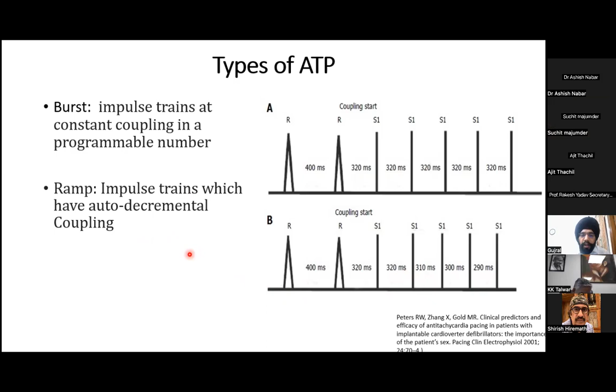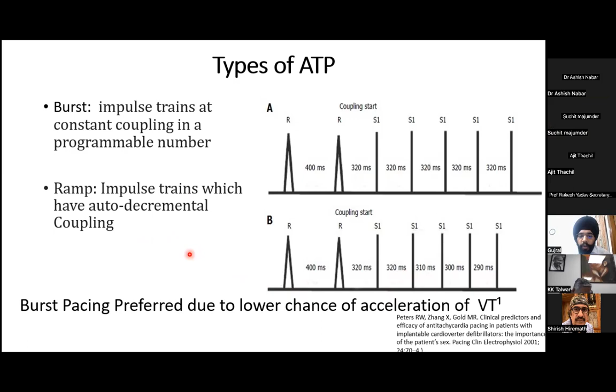Another type of ATP is possible, called ramp therapy. In that, the coupling interval between the pacing impulses is going to have a decrement, that is, it is going to reduce. The usual decrement that is set is 10 milliseconds. So here you can see the pacing impulse coupling interval is reducing by 10 milliseconds in every beat. This is called a ramp, similar to an inclined ramp that we talk about. Usually we prefer burst pacing because trials have shown a lower chance of acceleration of VT.